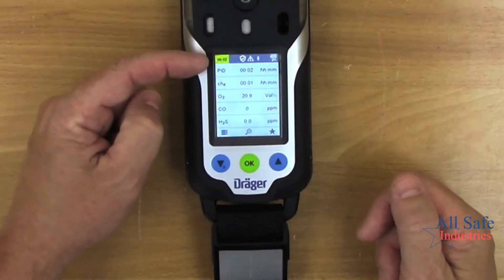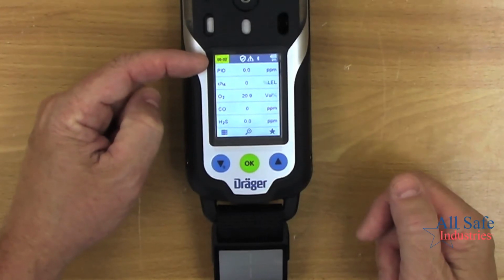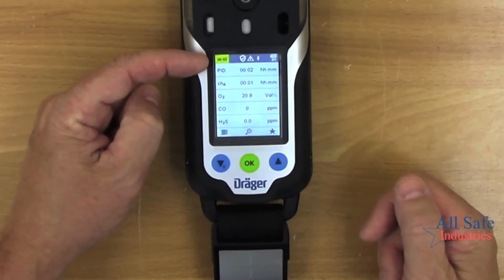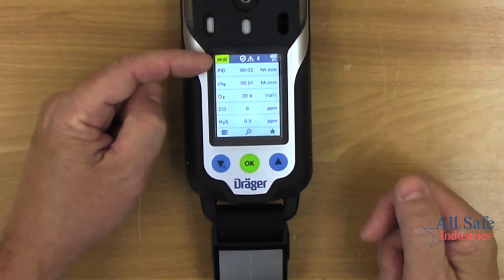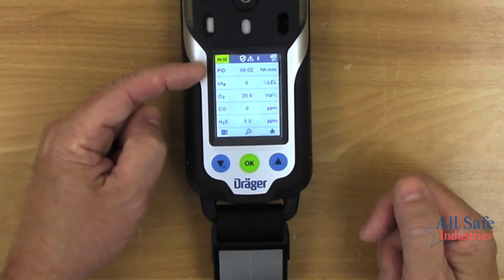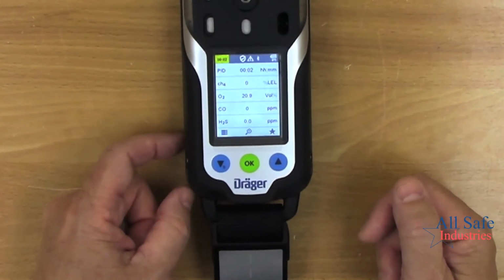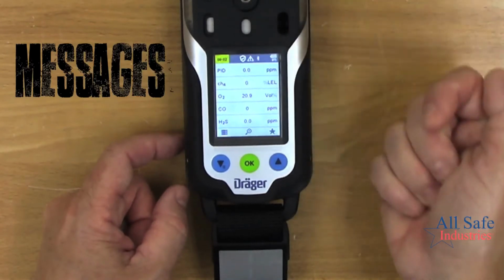When you see this yellow block at the top, that's Draeger's way of showing you that some of the sensors are still warming up. We'll want to make sure that's done with its countdown before I go out and use the instrument in the plant site. But you'll notice that I'm already in monitoring mode.